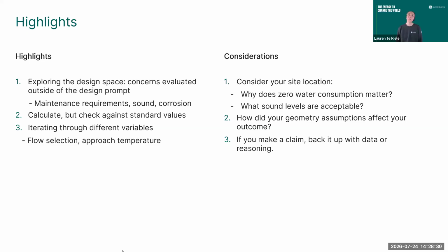I was Googling right before this, and a standard wet cooling tower is about 30% convection and 70% latent heat. So you could say, okay, I'm going to do the same thing as an air cooled condenser and be only convection. But I wonder if the thought is, even if you're only 10 or 20% latent heat in a very humid climate, maybe that's worth it, because that's so much more power dense than the equivalent airflow needed for convection. Yeah, it's possible. I don't know.